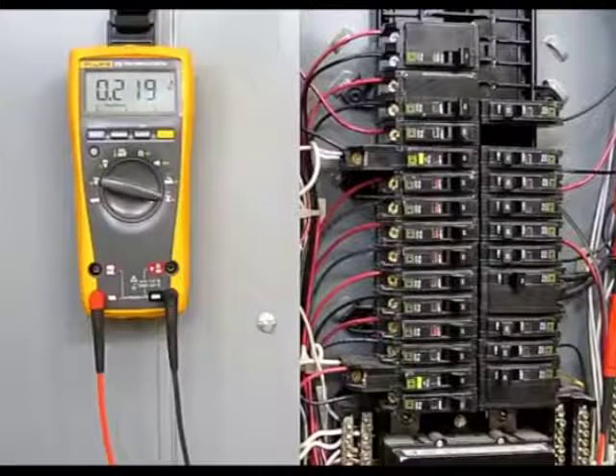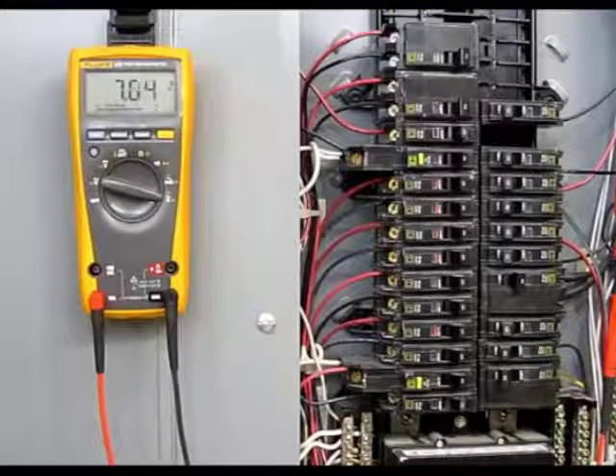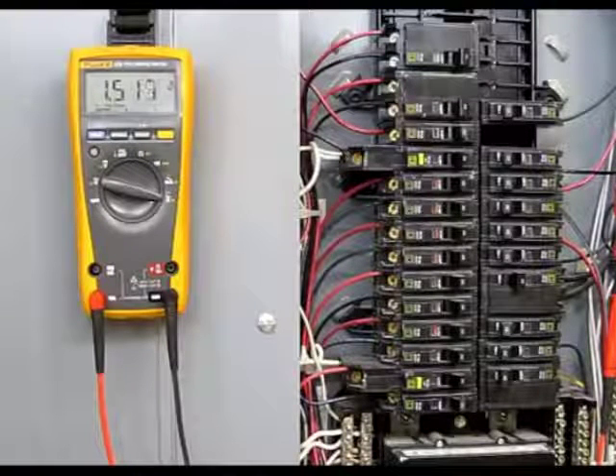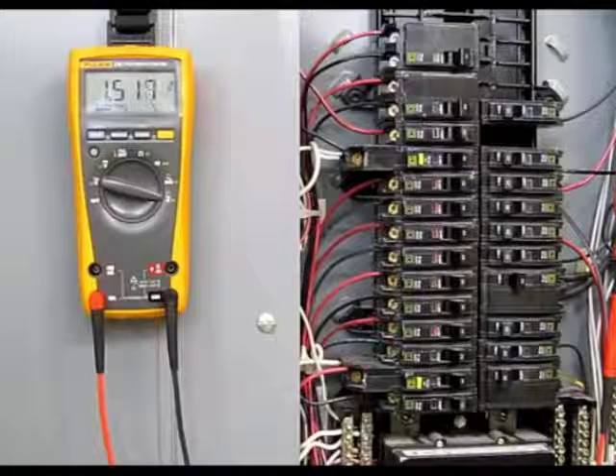In this video, we're performing an inline current test. We have de-energized the system and placed the meter in line with the circuit. When the circuit is energized, the full load current on that circuit is flowing through the meter. This is done on systems that have a low current draw.